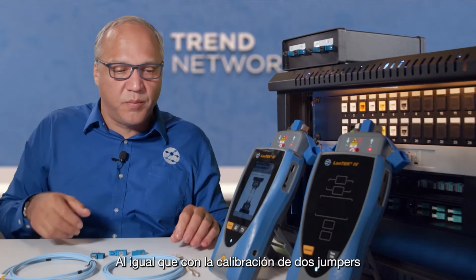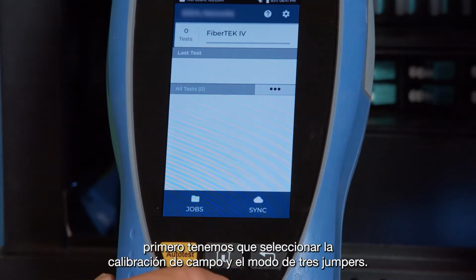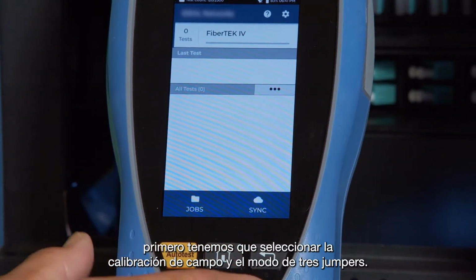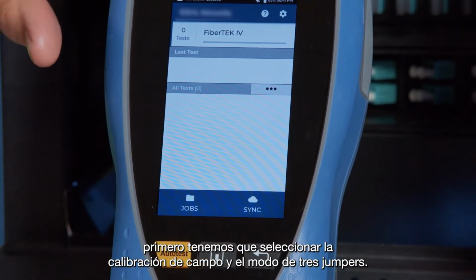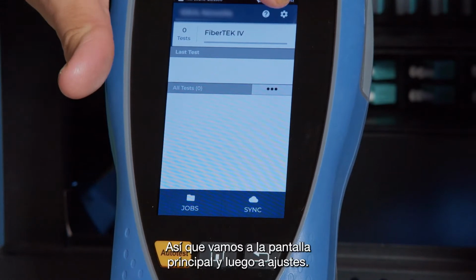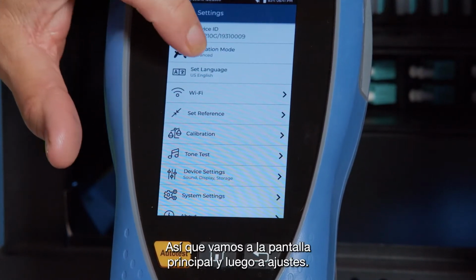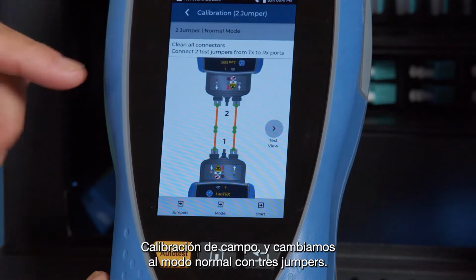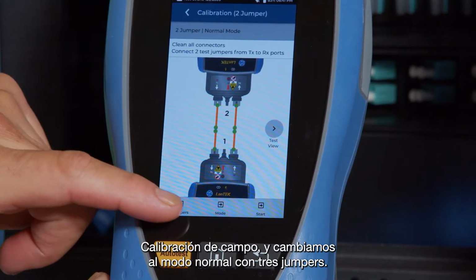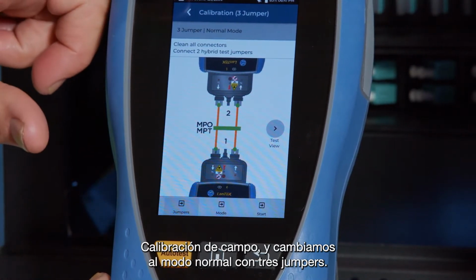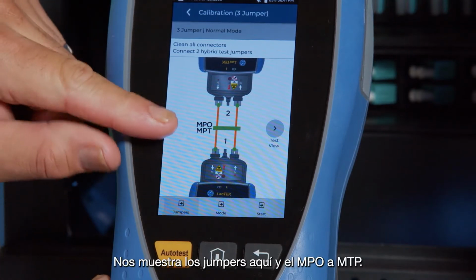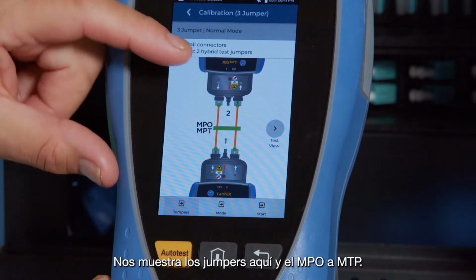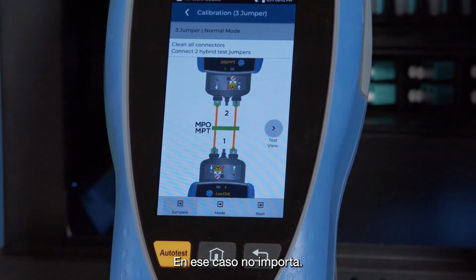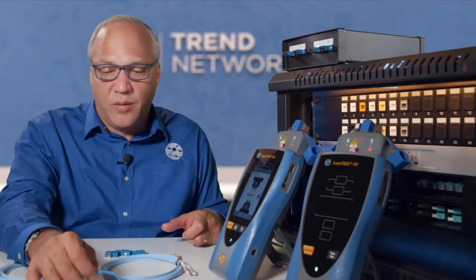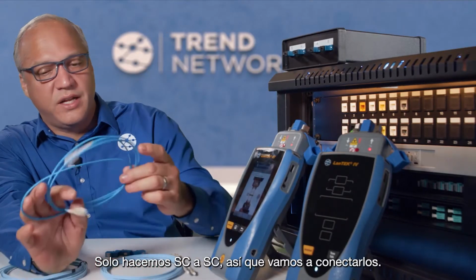So like with the 2-jumper calibration, we need to start by first doing our set reference, and we'll set it in the 3-jumper mode. So we go to the home screen, then go to preferences, set reference, and we'll change it to the 3-jumper normal configuration. So it shows the set of jumpers here and an MPO to MTP. So it doesn't matter in that case. We are just doing SC to SC.